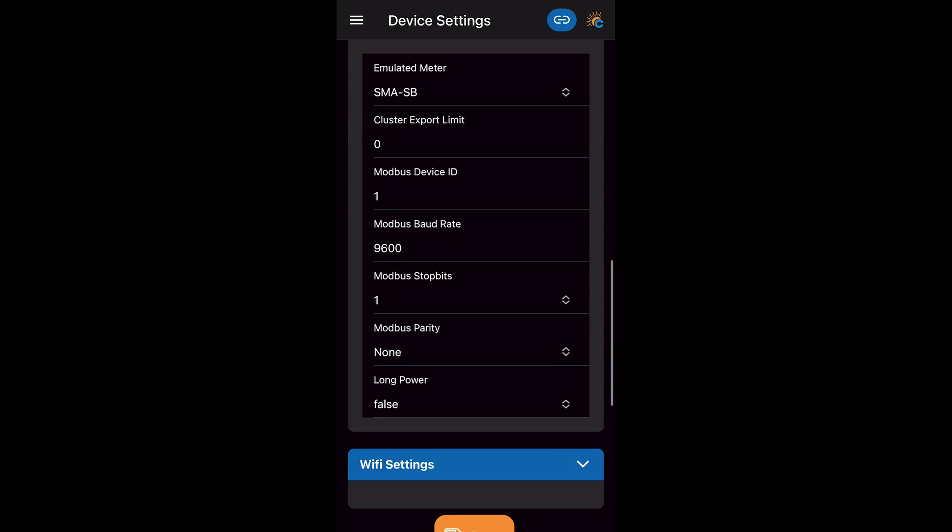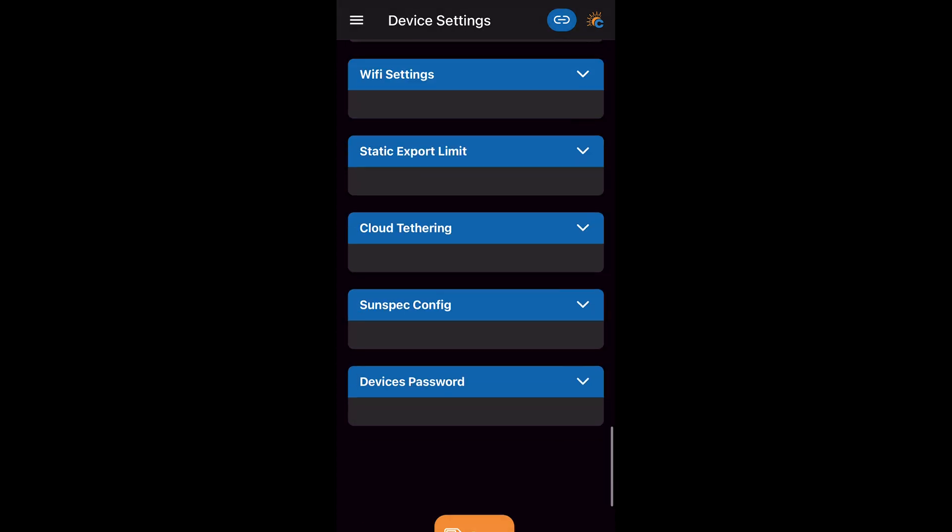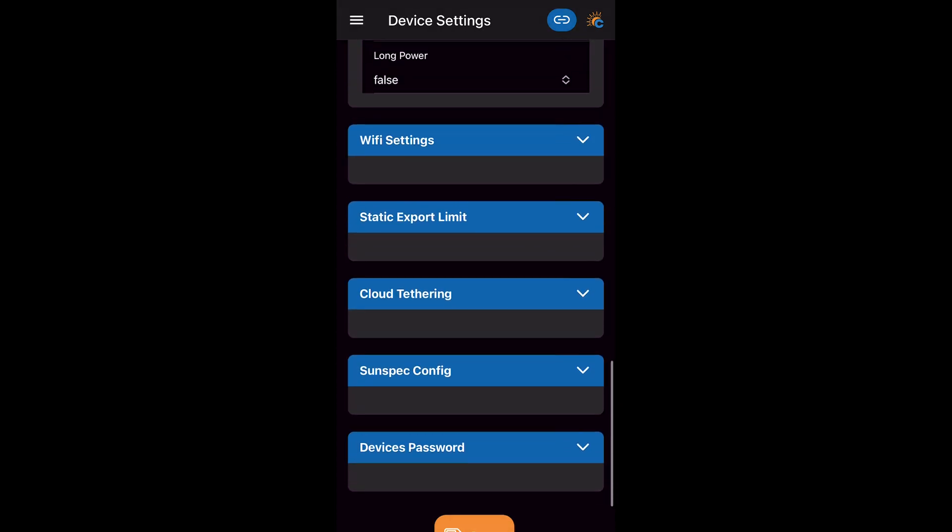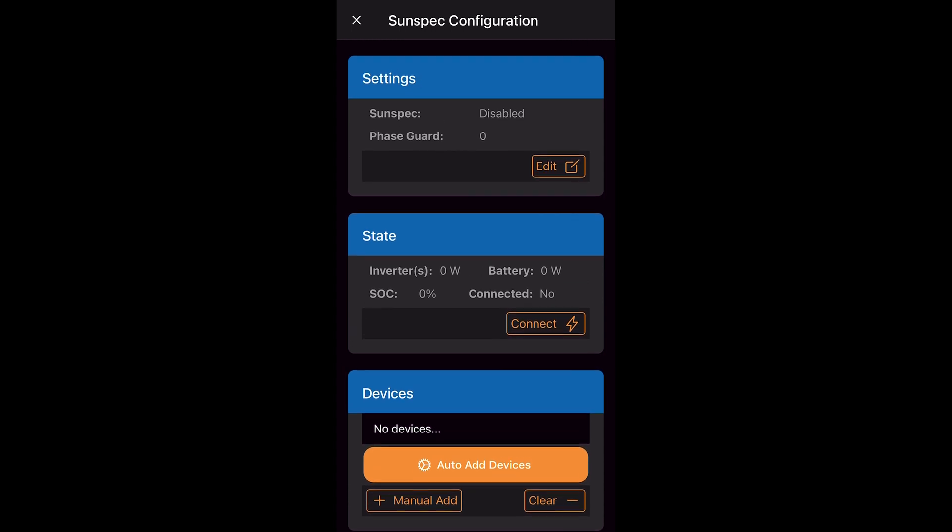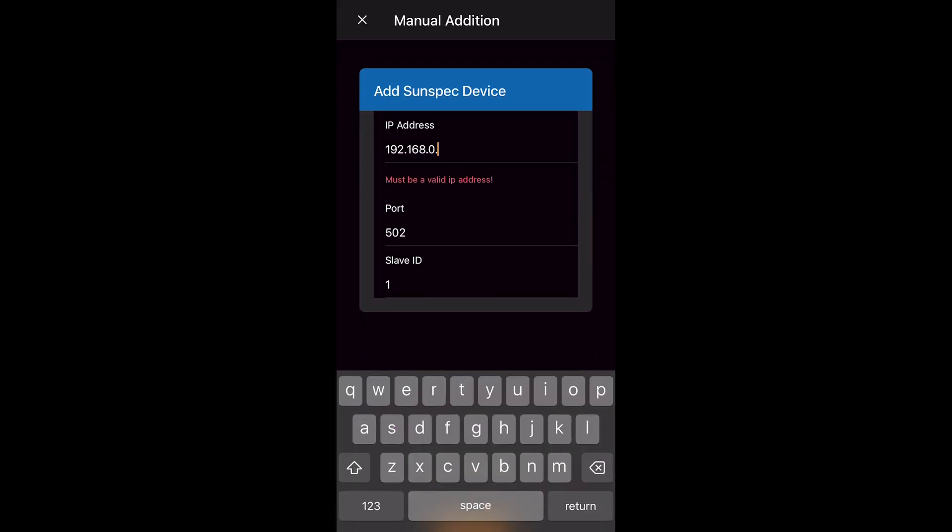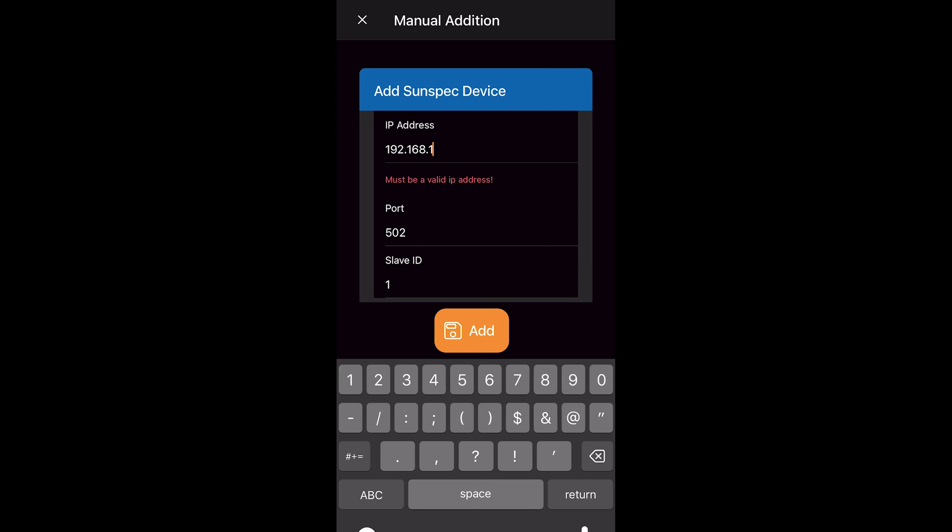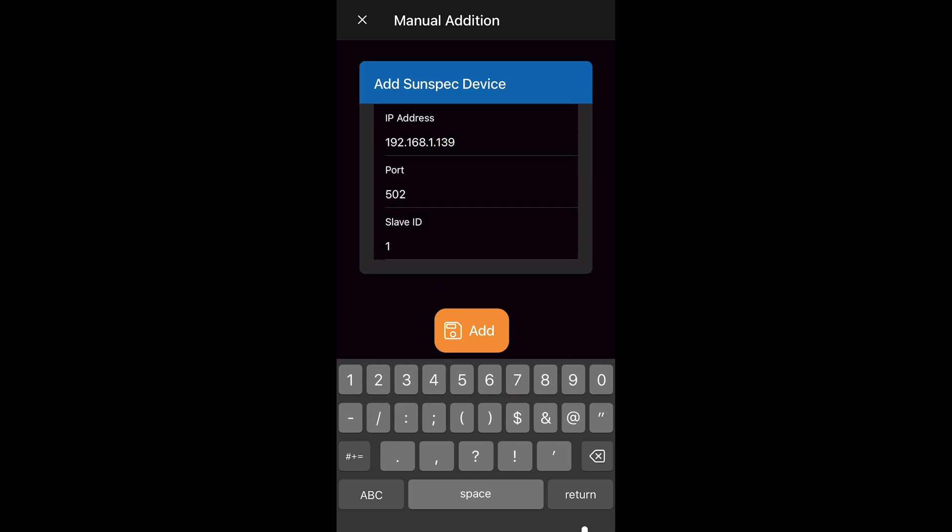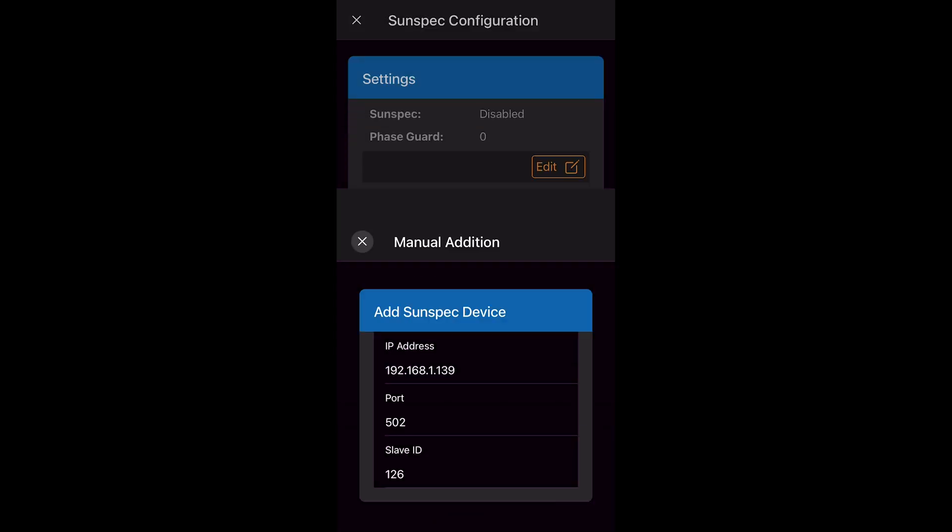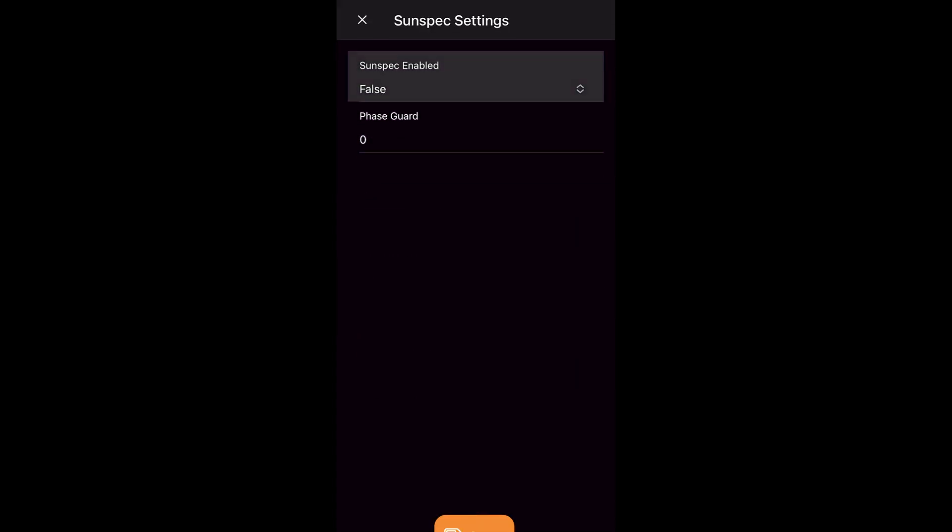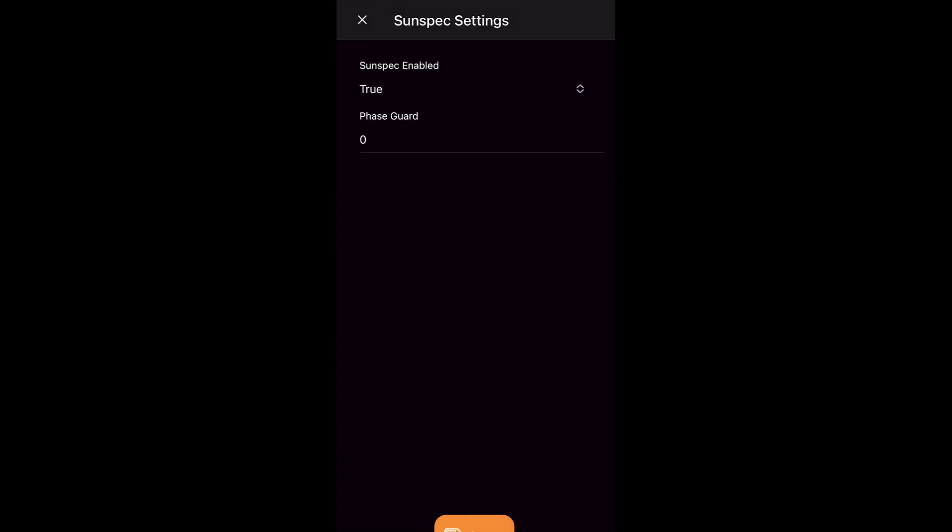We check our Modbus configuration for SMA Sunnyboy. Now that's good we go to SunSpec configuration. We go to manual add on the bottom left and we add the IP address of our Sunnyboy. Ensure the port is set to 502. And we change the slave ID to 126 and click save. We have now found our Sunnyboy inverter. Our SunSpec settings we change to true.